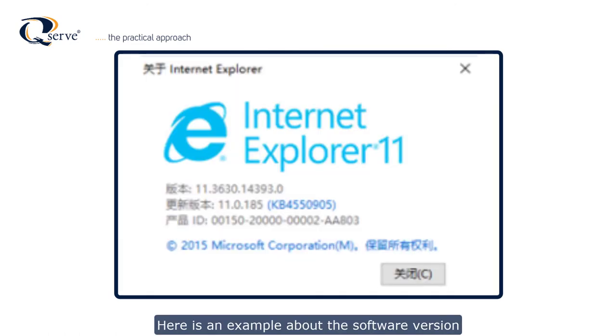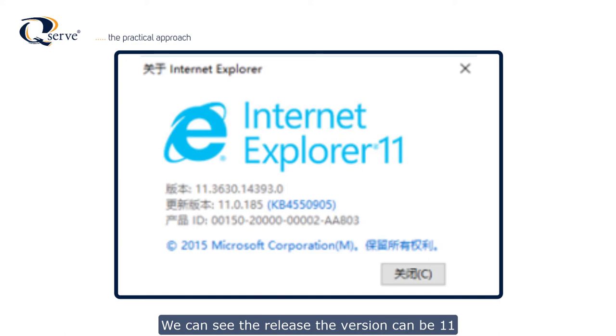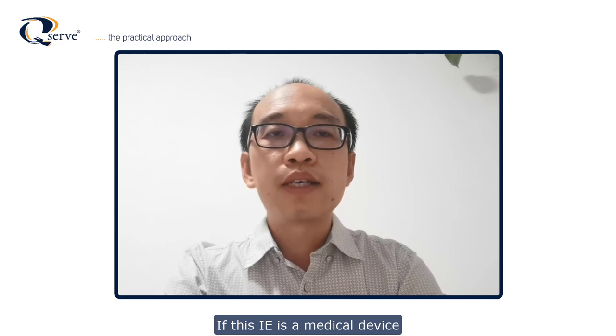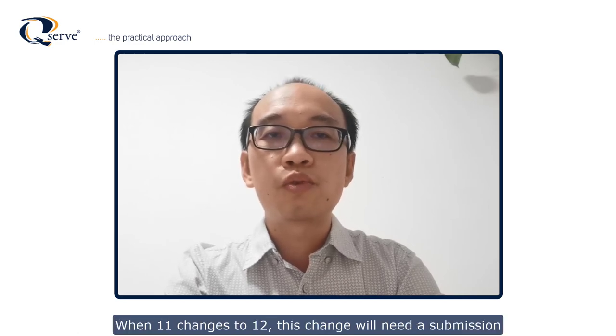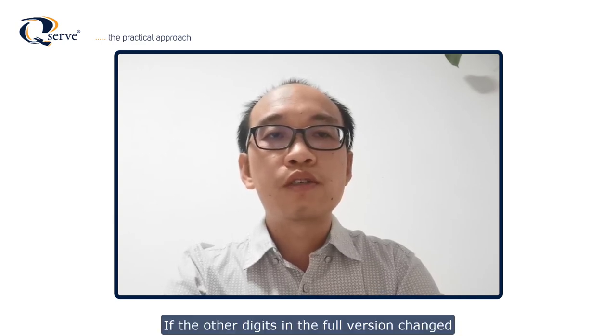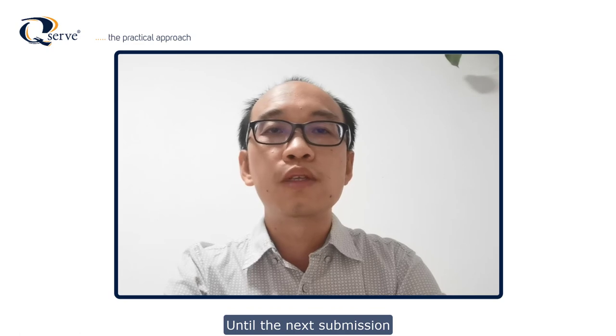Here is an example of software versioning using Microsoft Internet Explorer. In the about box, we can see the release version is 11, and its full version is 11.3630.14393.0. If this IE were a medical device, when 11 changes to 12, that change would require a submission. If the other digits in the full version changed, those changes can usually be recorded in the QMS until the next submission.